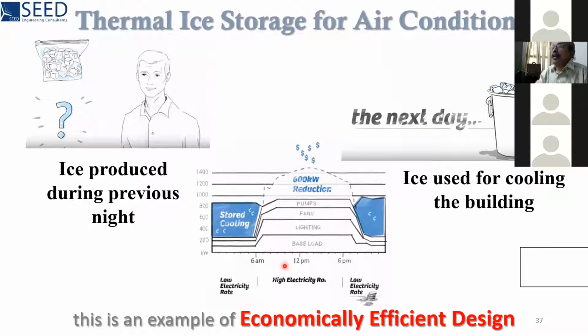On the contrary, during night, sun is not present. Most of the offices are closed. So the electricity demand is less. When your electricity demand is less, you are charged less. Take advantage of the lower tariff and produce ice the previous night. Ice produced during the previous night is used for cooling the building. Cooling the building means cooling the chilled water during the peak hours.